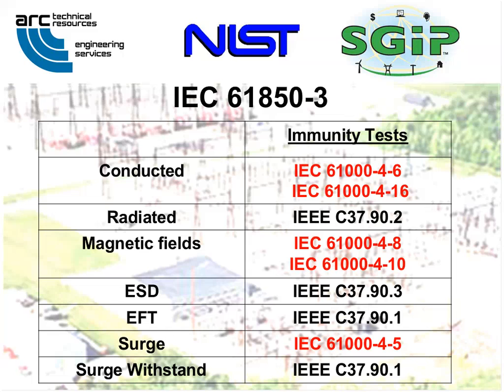For instance, for radiated RF fields, it would be 61000-4-3. For ESD, that would be 61000-4-2. EFT would be 61000-4-4, for instance. Surge withstand would be 4-5, for instance. If we found that the American document under IEEE was already doing the test, even if it was more severe or a different level or something, we didn't second guess it. We just concluded it was not a gap. The five shown in red here are the gaps, meaning there was no IEEE equivalent for this.